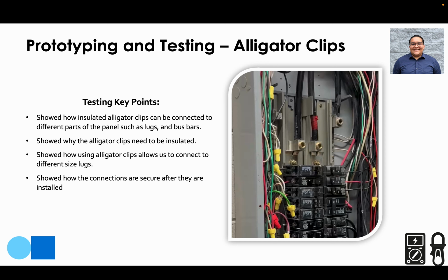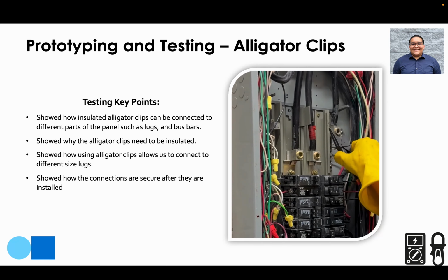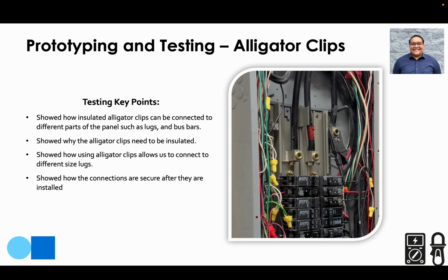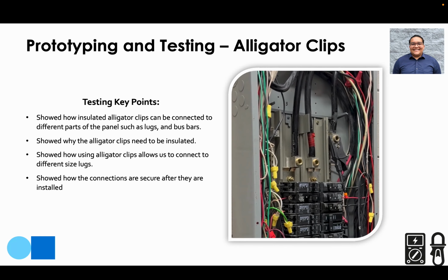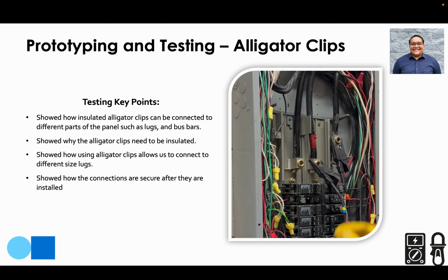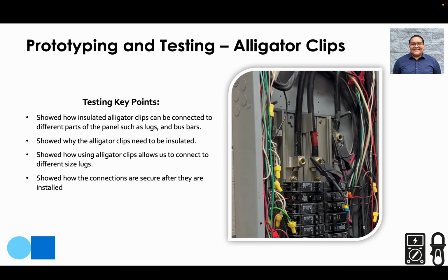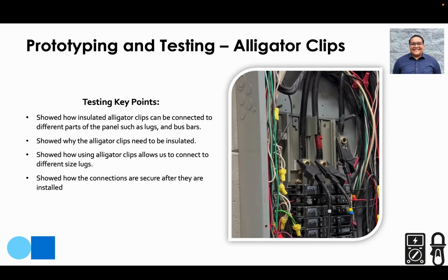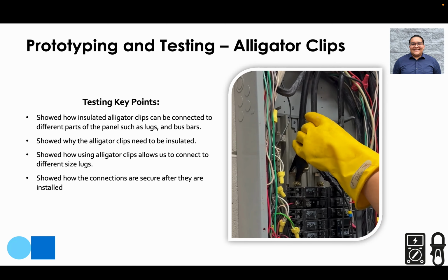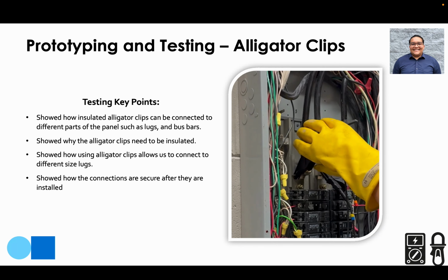To show why we are using alligator clips for our voltage measurement device for this project, we made the video on the right. First, it shows why it's important to use insulated alligator clips in electrical panels, as there are a lot of metal parts and touching those can cause an arc flash. It shows the versatility of alligator clips, as they can be installed in different size electrical lugs and even bus bars if necessary. And it shows that after the connections are done, they are secure, which allows us to have a permanent logger installed without fear of connections falling off.